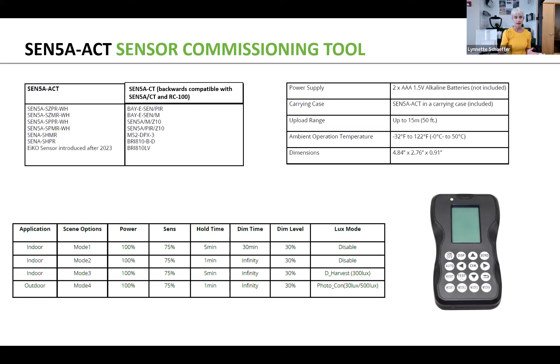Each of these sensors acts individually. This is 100% not a network lighting control system. Every sensor needs to be programmed and commissioned using the commissioning tool, and they all act independently from one another as you walk through the space. So no grouping, no zoning, none of that kind of stuff.